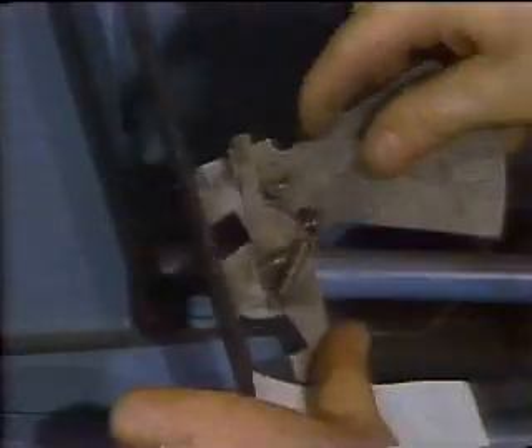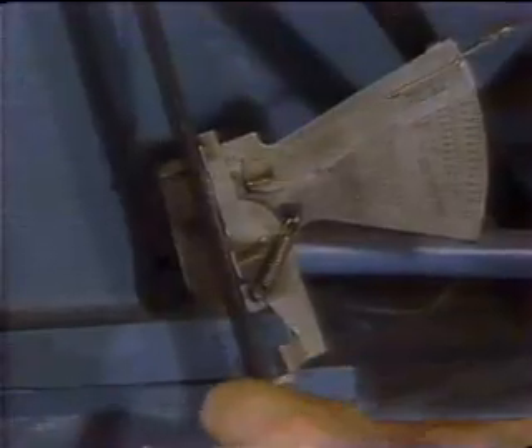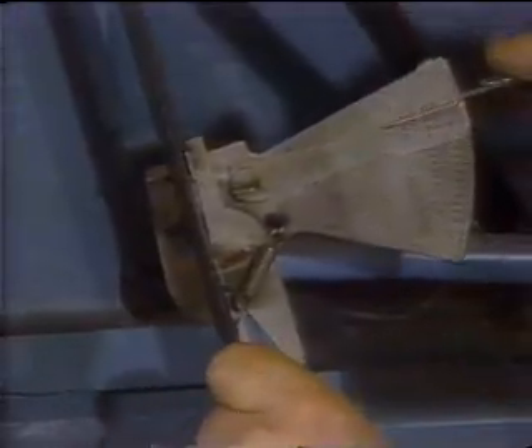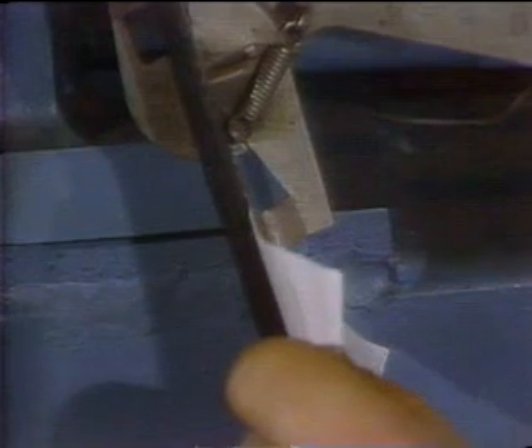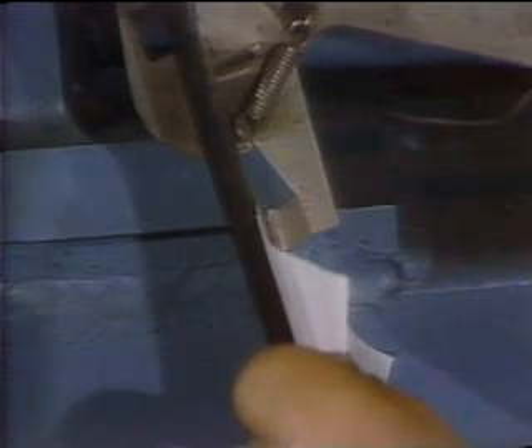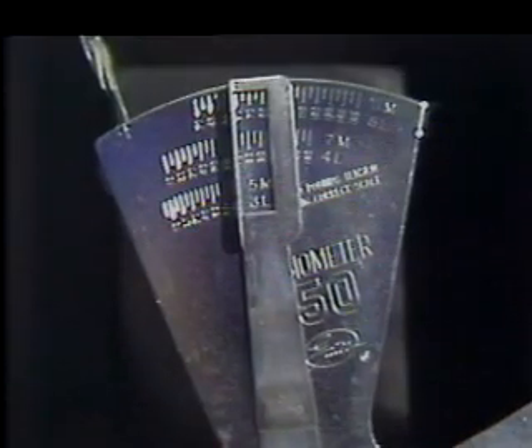It fits on the belt like this. The pivot point should be halfway between the two sheaves. Make sure that this indicator hand is all the way up. Hold a sheet of paper between the belt and this lower arm. Press down on the lever until the lower arm is just touching the paper. Then let go of the lever and take the gauge off. Now look closely at the indicator hand.